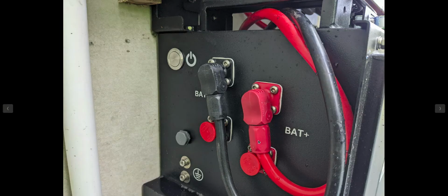Now, what else? He said something about the earthing. And here we go. I haven't put any earth wires on here. Why are there 2 earth wires? It's because that's for putting extra battery packs adjacent to this one. You have to link it with a battery earth wire as well as the 2 extra battery cables. But between the battery and the inverter, yeah, I could put an earth wire on there, but I'm only going to bolt it to one of these mounting bolts anyway, because the inverter itself doesn't have these. So these are more like battery to battery earthing terminals, and I tested it. It was earth, and the inspector seemed to be happy about that.